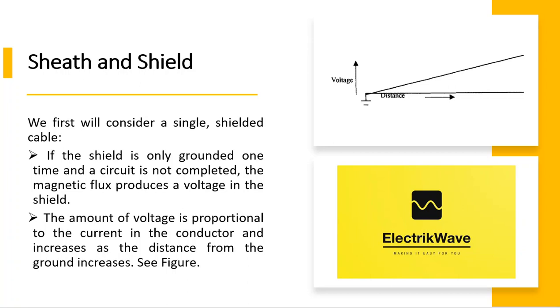We first will consider a single shielded cable. If the shield is only grounded one time and a circuit is not completed, the magnetic flux produces a voltage in the shield. The amount of voltage is proportional to the current in the conductor and increases as the distance from the ground increases.